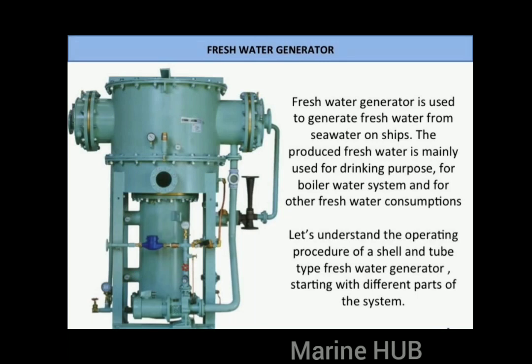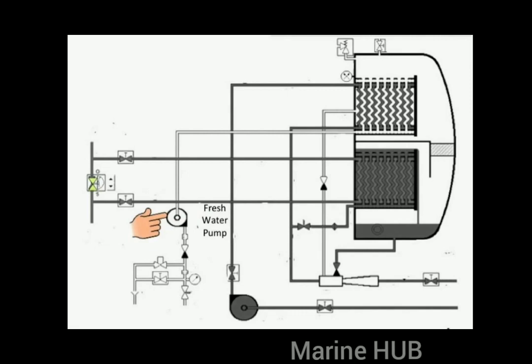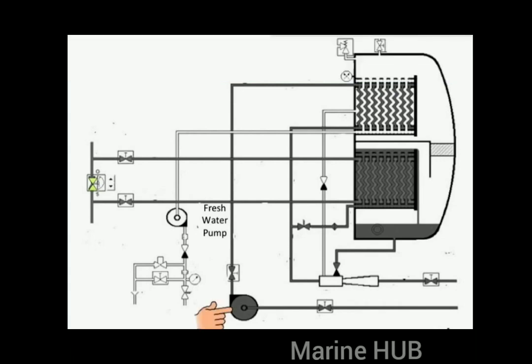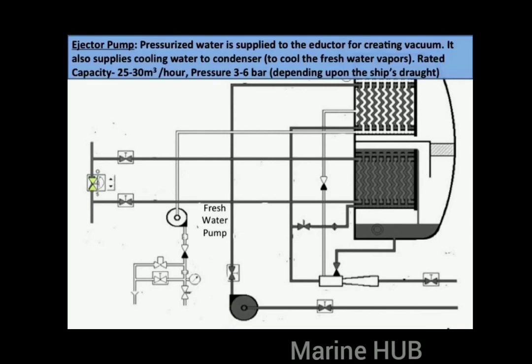The first component of the fresh water generator is the fresh water pump, which is used to supply the generated fresh water to the ship's fresh water tanks by taking suction from the generator. The normal rated capacity varies from 3 to 5 cubic meters per hour, depending mainly on the supply head. The next component is the ejector pump, which supplies pressurized water to the eductor for creating vacuum and also supplies cooling water to the condenser. Its rated capacity varies from 25 to 30 cubic meters per hour at a pressure of 3 to 6 bar.